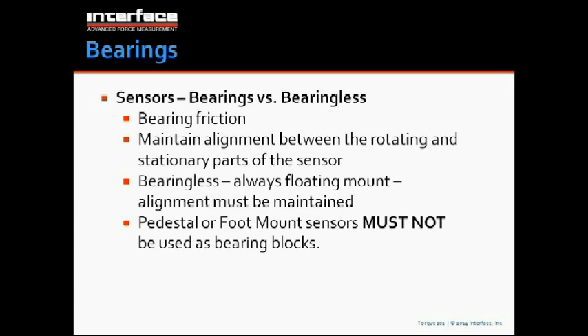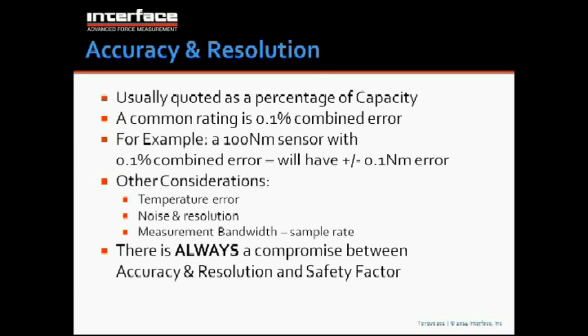In a bearingless sensor, the user is required to maintain that alignment, and so it makes installation a little more tricky. Bearingless are always floating mount. And once again, I'm going to say a pedestal or foot mount sensor must never be considered as a bearing block. It's just to allow the sensor to be positioned, but it's not supposed to allow radial loads into that sensor bearing because it's not designed for that.